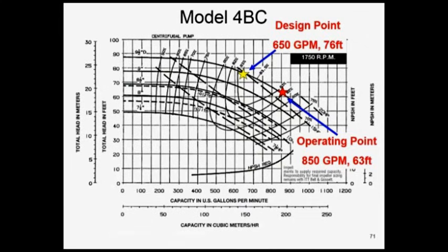If my pressure drop is 63 feet versus 76, what is my flow rate? I'm not underperforming flow-wise. I'm overperforming. So you see the red star? The yellow star is design. It's where you thought you'd be. The red star is where you really are. And if you take the red star on that impeller of 9.5 inches, that's where you've got to be, with 63 feet on the vertical axis. Read straight down. What is your flow rate?